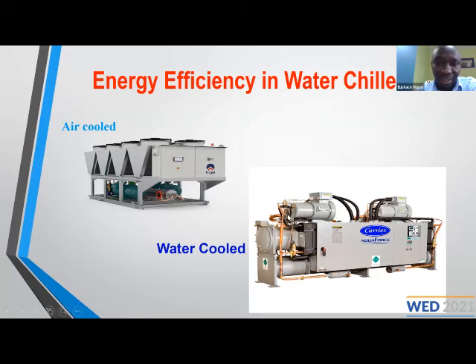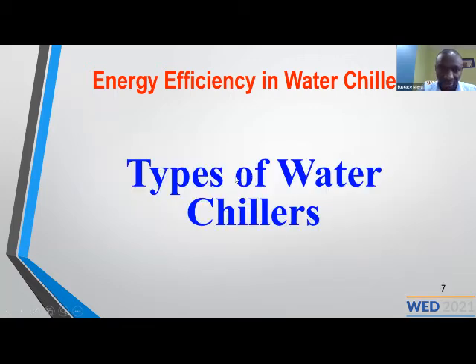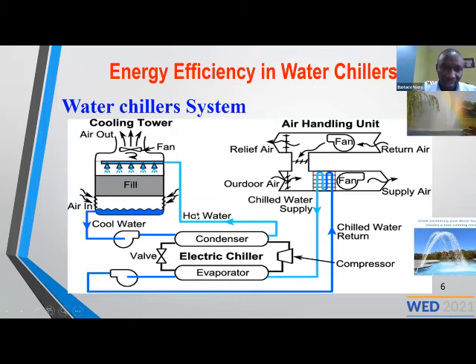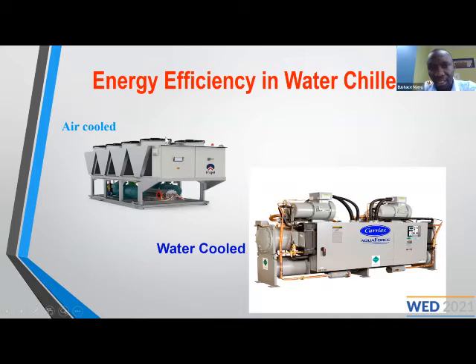Because if it's a very big load, you need to employ a water cooled chiller. But for relatively small loads, it will be inefficient to use the water cooled chillers. So you have to check, and we are going to show the ranges of cooling loads, so that you can understand the situation. You have to use the air cooled chillers. In air cooled chillers, you can see there are fans. These fans are the ones which are used instead of using a cooling tower, which is in a water cooled chiller. That's what you have in the air cooled chillers.